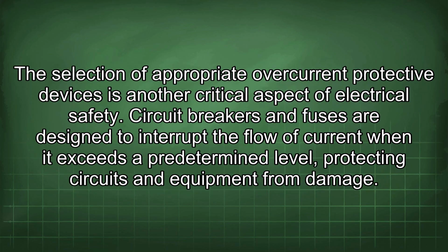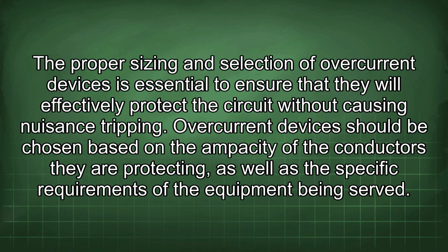The selection of appropriate overcurrent protective devices is another critical aspect of electrical safety. Circuit breakers and fuses are designed to interrupt the flow of current when it exceeds a predetermined level, protecting circuits and equipment from damage. The proper sizing and selection of overcurrent devices is essential to ensure that they will effectively protect the circuit without causing nuisance tripping.